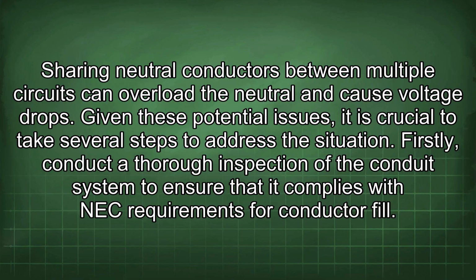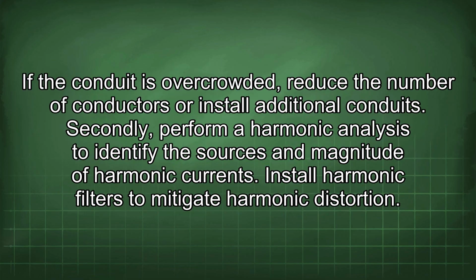Given these potential issues, it is crucial to take several steps to address the situation. Firstly, conduct a thorough inspection of the conduit system to ensure that it complies with NEC requirements for conductor fill. If the conduit is overcrowded, reduce the number of conductors or install additional conduits. Secondly, perform a harmonic analysis to identify the sources and magnitude of harmonic currents. Install harmonic filters to mitigate harmonic distortion.